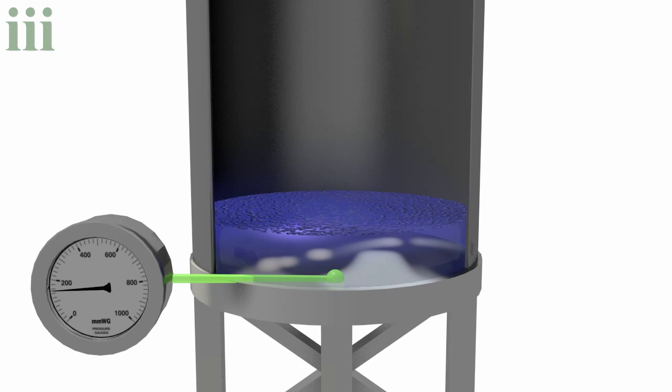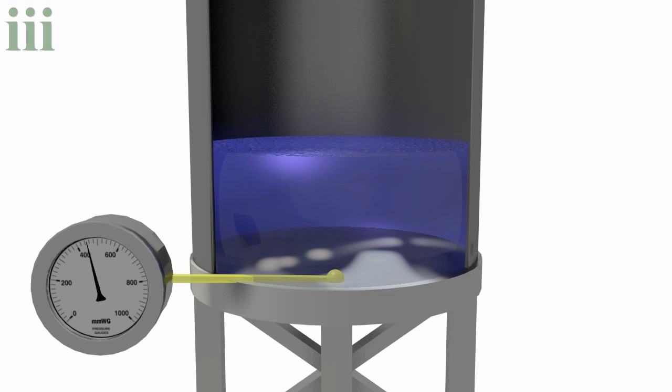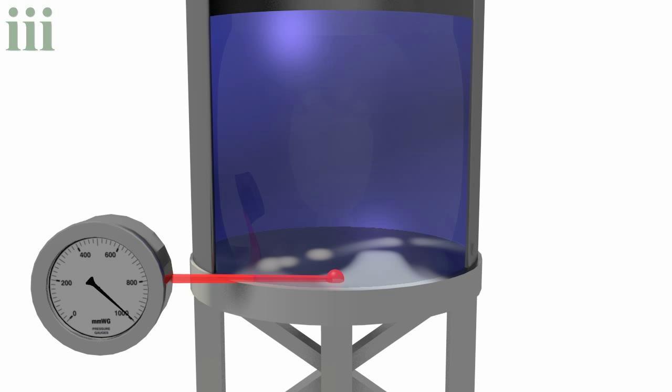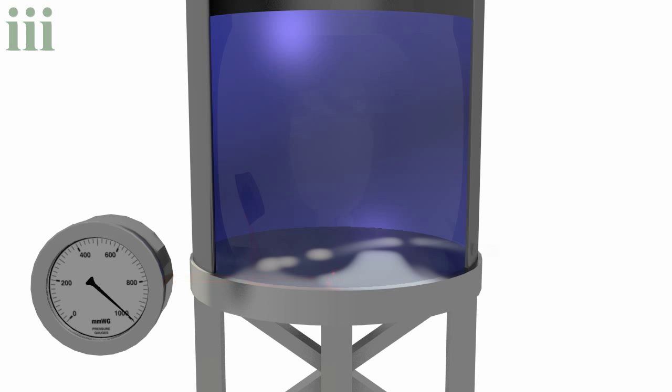So by picking a fixed point underneath your liquid and measuring the pressure, you can very accurately measure the depth of the water above that point.